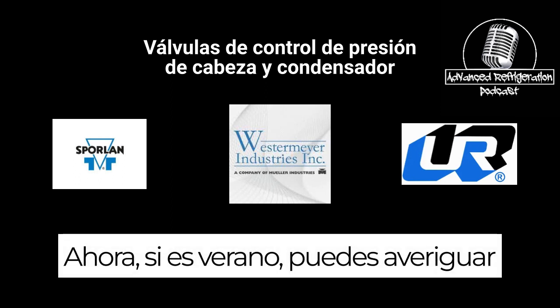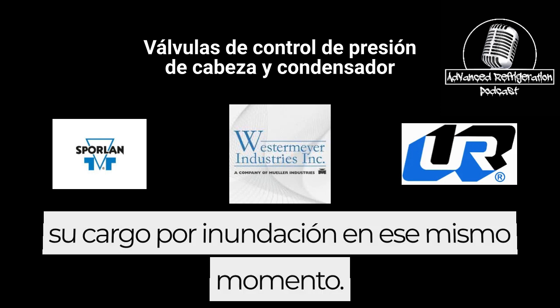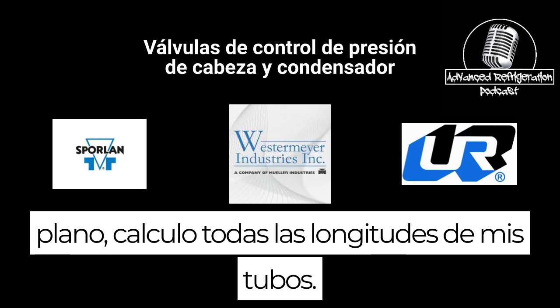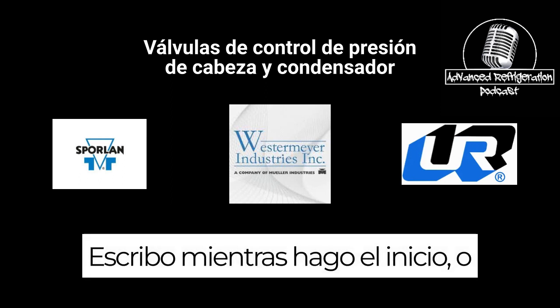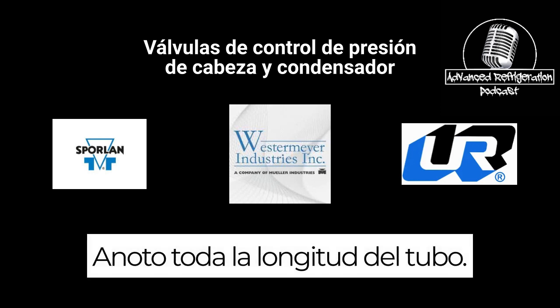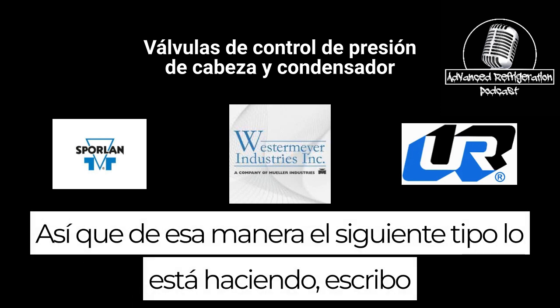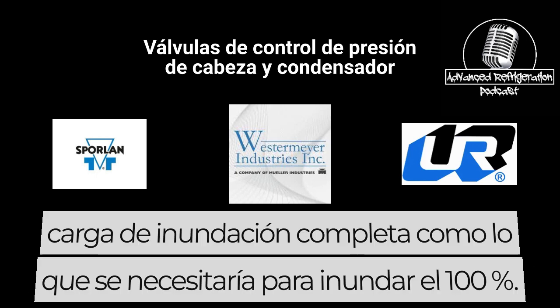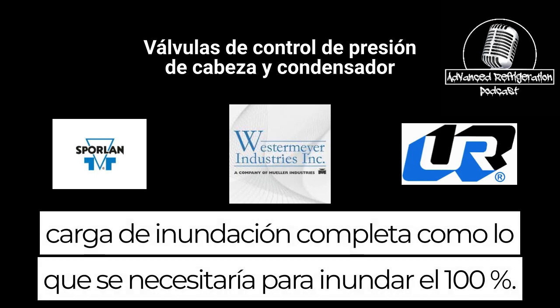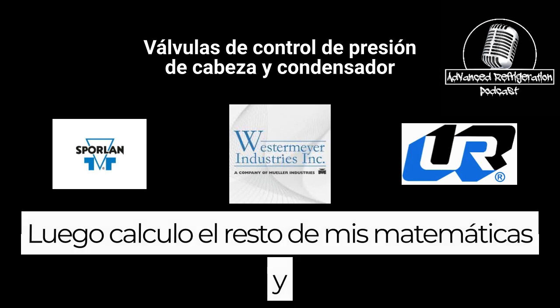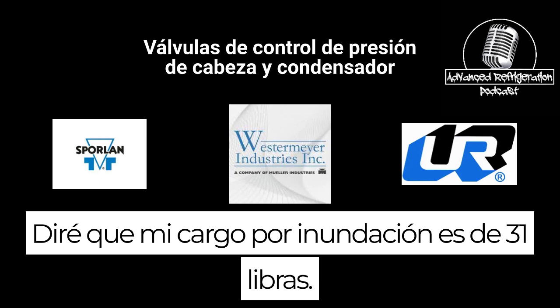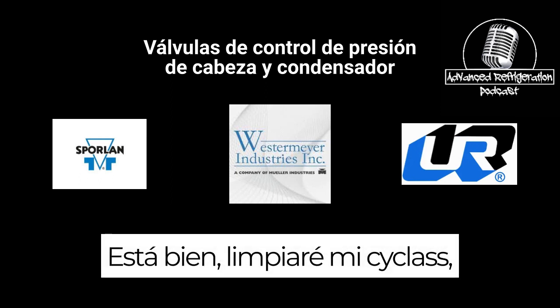Now, if it's summertime, you can figure out your flooding charge right then and there. If you start this unit up, I figure out all my tubing lengths. I write down the entire tubing length as I'm doing startup, so the next guy doesn't have to do it. And I write down the entire flooding charge, what it would take to flood 100%. Then I figure out the rest of my math, and I'll say my flooding charge is 31 pounds. Okay. Well, I'll clear my sight glass.